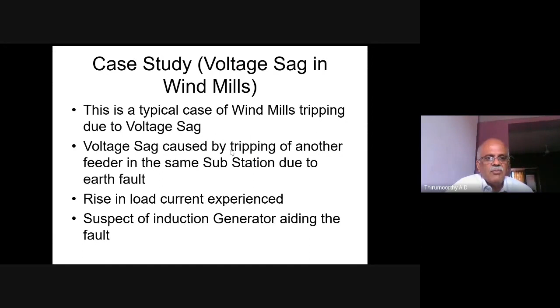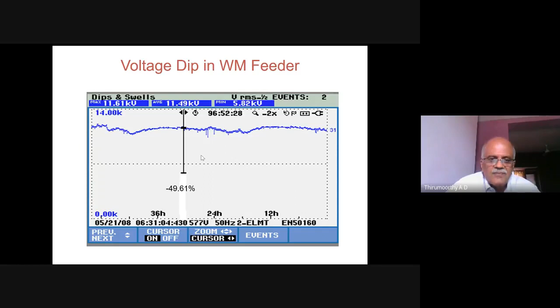This is actually to show the case study of how the windmills react to this condition. So you can see in this trend that has been recorded in a substation where predominantly windmills have been connected in Tamil Nadu, one such event has been recorded, and the voltage drops by nearly 50% at a given moment. During that moment, nearly 50% of the windmills have tripped. This is a windmill generation graph trend. More than 50% of the windmills have tripped here at the same moment.